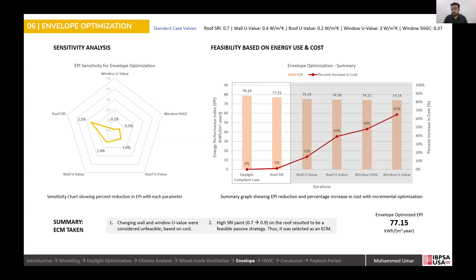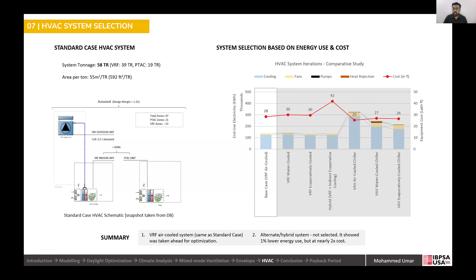Coming on to the HVAC system optimization, the first part is selecting the right HVAC system, then optimizing it further. In the standard case HVAC system, the system tonnage was 58 tons, with 23 zones catered to by a VRF system and 21 catered to by PTAC units. In the end, when energy use and cost are looked at, the base case itself was the most feasible, because it showed the most feasible energy use with the equipment cost. You can see here that even a hybrid system was tested. It showed 1% lower energy use, but at nearly 2x cost. Thus, the base case was taken forward.